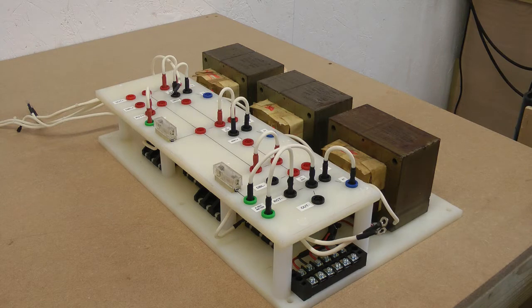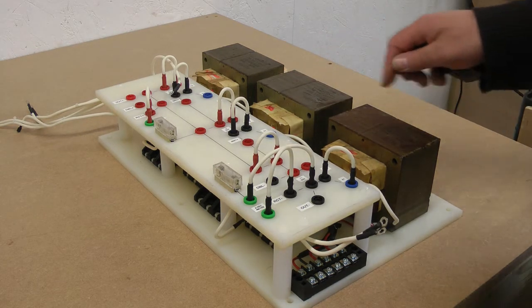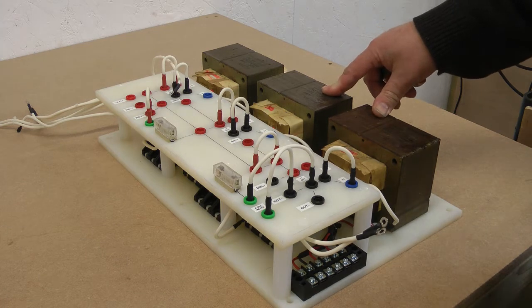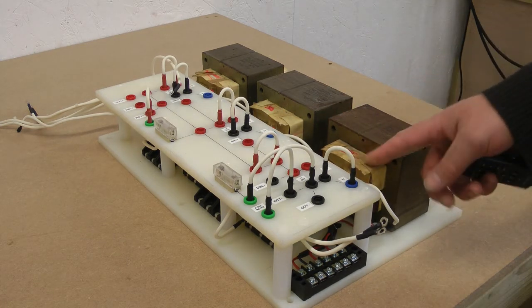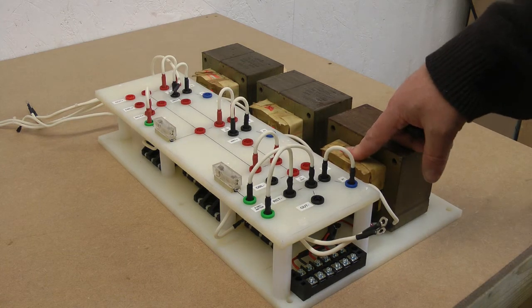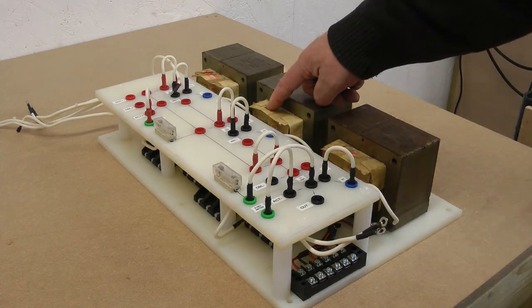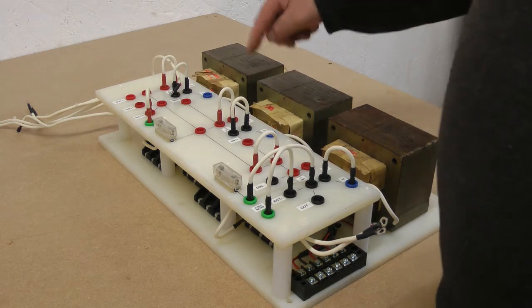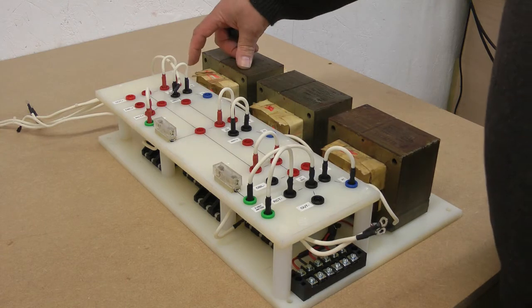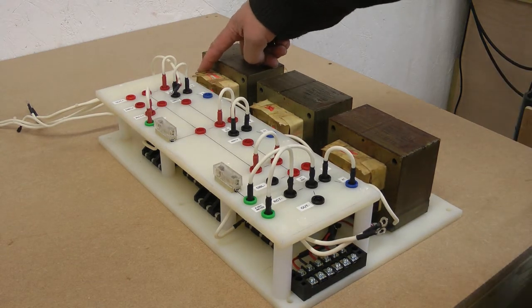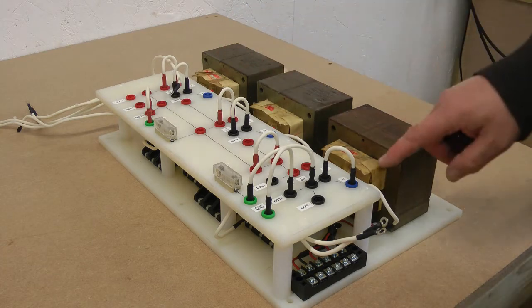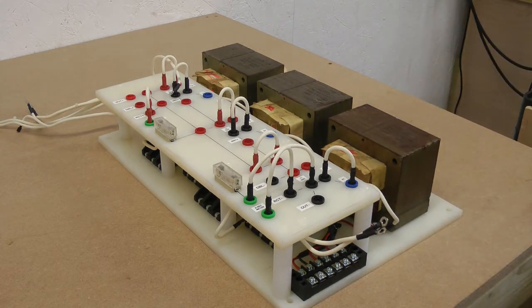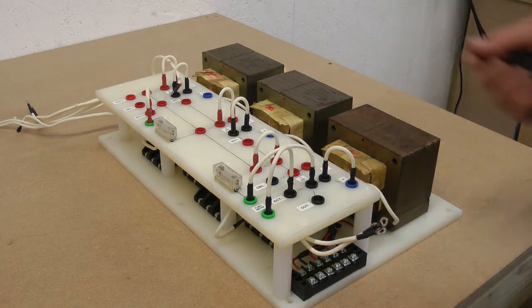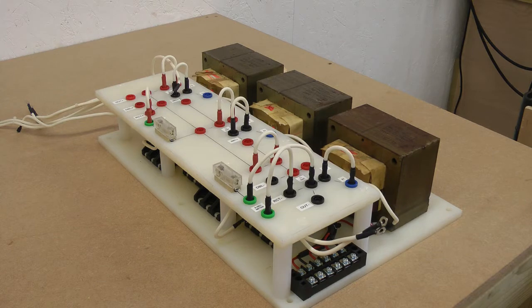If you want to connect all 3 in series, the trick is to join the 2 cores here together. This secondary, the lowest secondary, pushes downwards to minus 3 kilovolts. This one pushes up to 3 kilovolts. This core is floated at the end here, so it's at 3 kilovolts, and the output of the secondary here is at 6 kilovolts. So the entire potential difference across the 3 transformers is the 9 kilovolts, but you're never getting the primary too far. The primary to core is never getting close to a flashover point. Anyway, that's a more advanced way of running it.